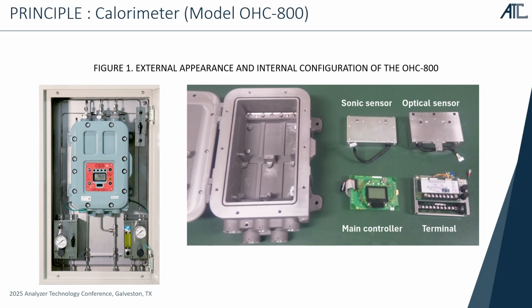And then since these are physical sensors, once we calibrate the sensor, no recalibration is required in the field. And then, as you can see, there are just screws to fix the sensors. So once some issue is caused on the sensor, just a quick swap is conducted by the customer. It's like 10 minutes. So this unit minimizes the downtime in the field.